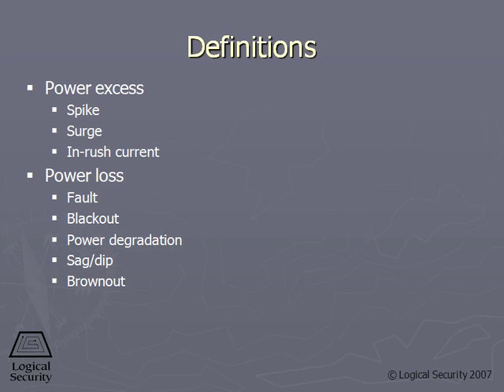The concept of inrush current has to do with, as we power on devices for the first 1 to 2 seconds, that device is drawing much more current than as the device is maintained in a powered on state. So as I power on a device, the current draw is very high for 1 to 2 seconds. After that, it stabilizes. That first 1 to 2 seconds of high amperage is called inrush current.